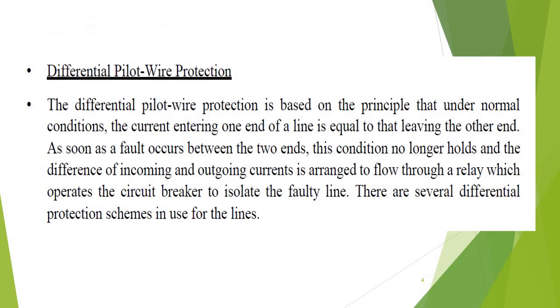In differential pilot wire protection, it is based on the principle that under normal operating conditions, the current entering one end of the line is equal to that leaving the other end. As soon as a fault occurs between the two ends, this condition is no longer valid. The difference of incoming and outgoing current is arranged to flow through the relay and operate the circuit breaker to isolate the faulty line.